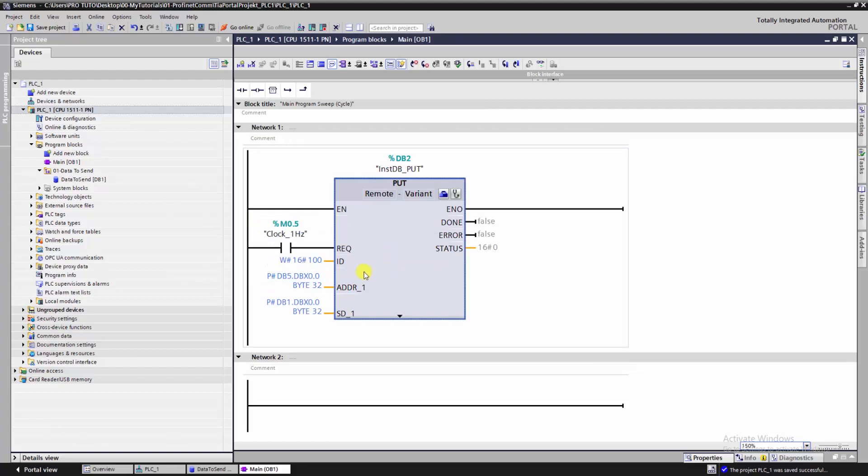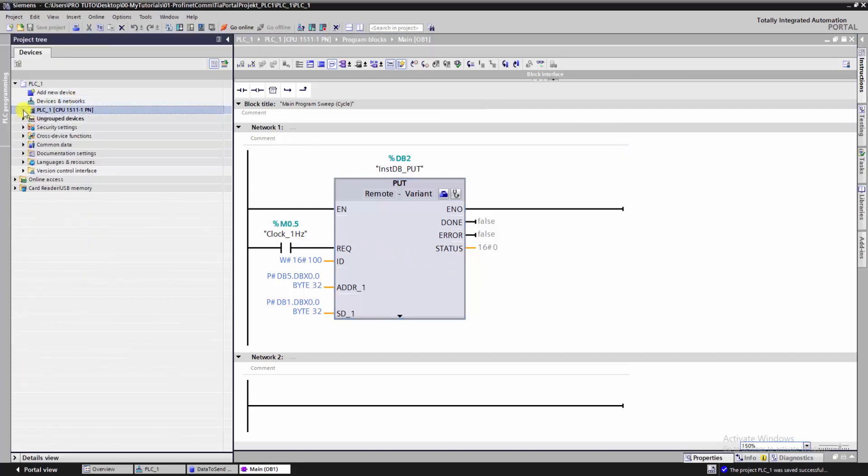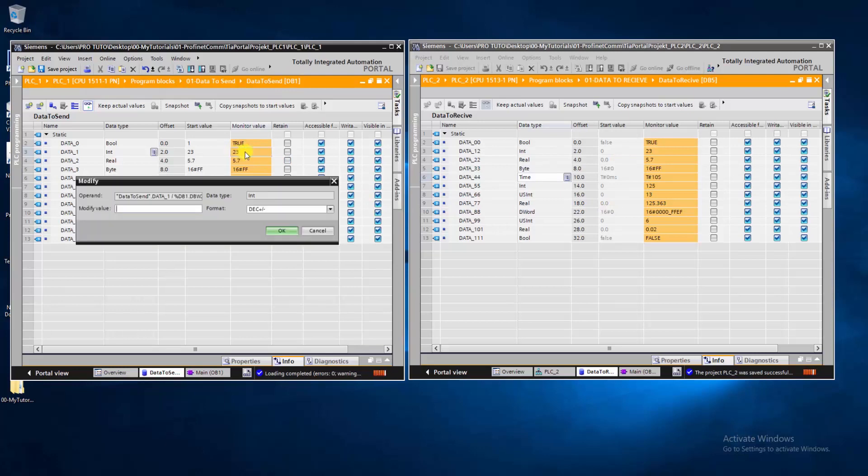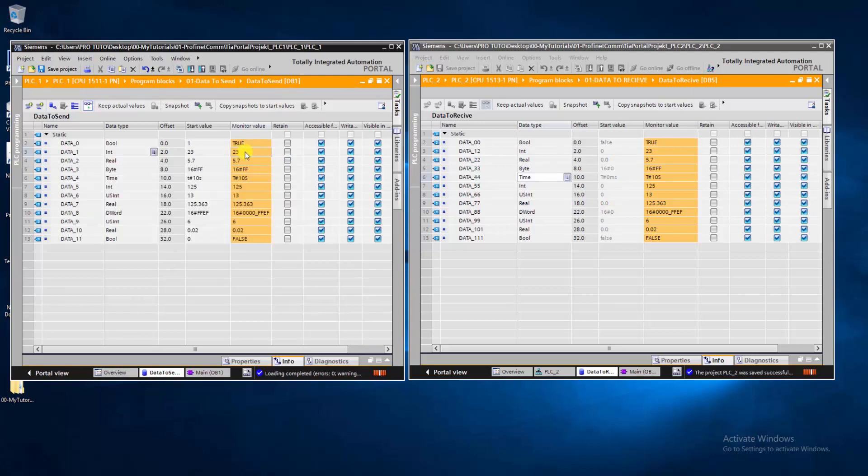Finally, we can use PLC SIM Advanced and upload the two programs to the two CPUs. When you upload the two programs, but data was not sent from PLC to PLC, we should make sure that both PLCs allow the put and get option.